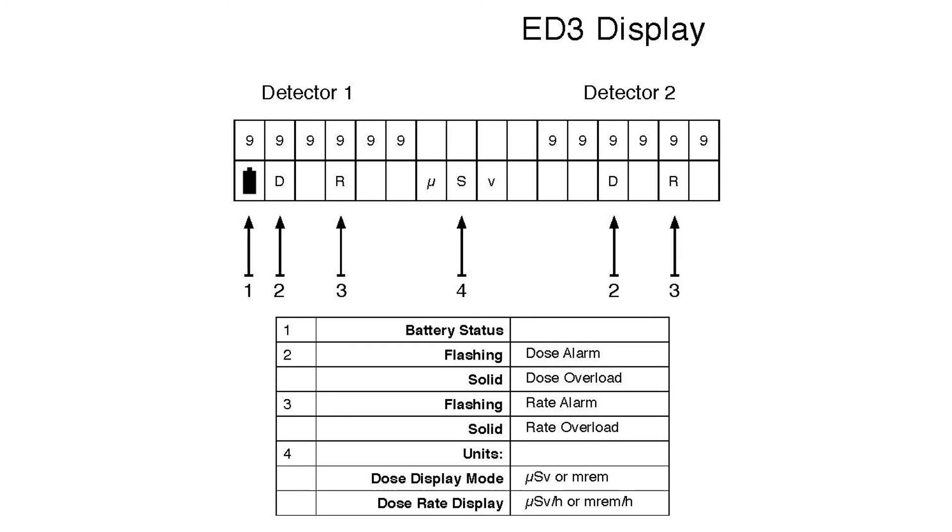And when the alarm sounds, the unit will actually start to flash the display. Should the display be solid and the alarm still sounding, this means it's in dose overload or dose rate overload mode and not accurately measuring dose anymore or the dose rate anymore due to the overload of the electronics or the detector.